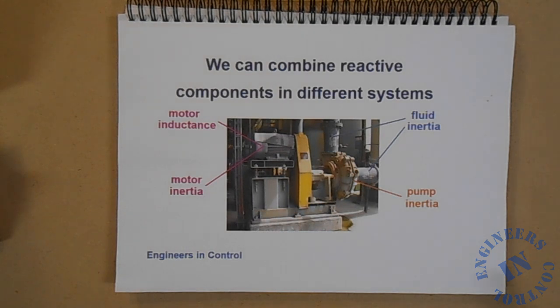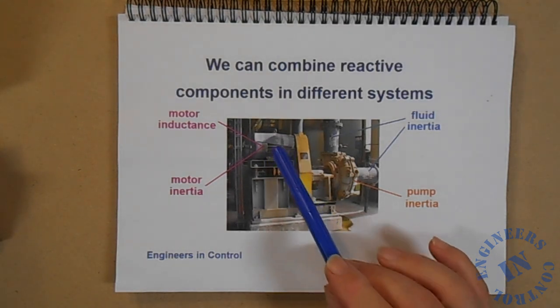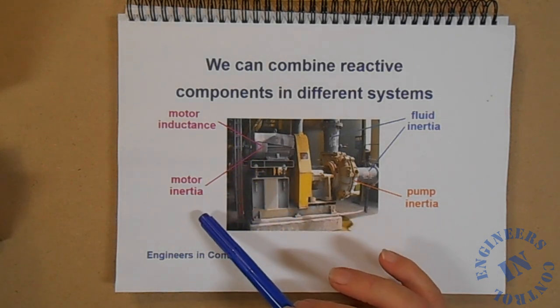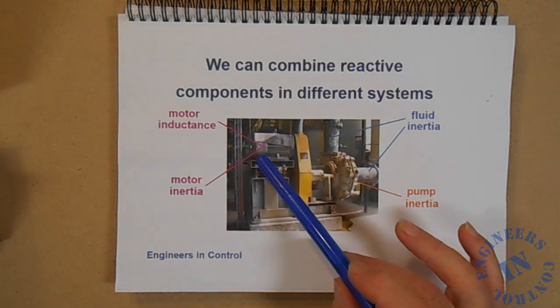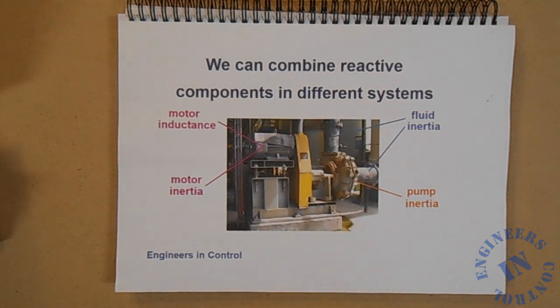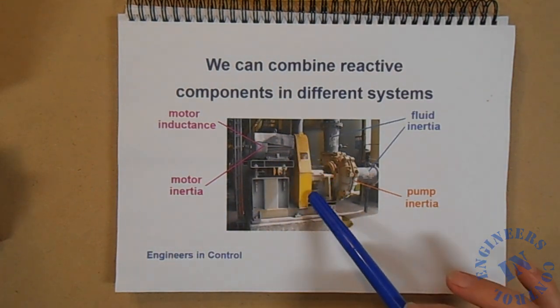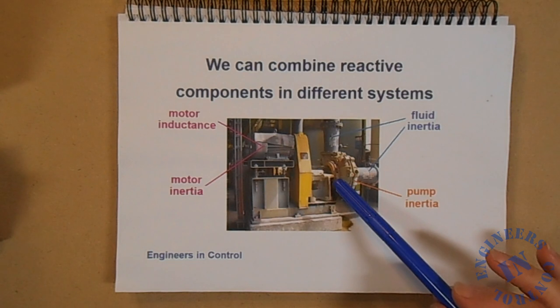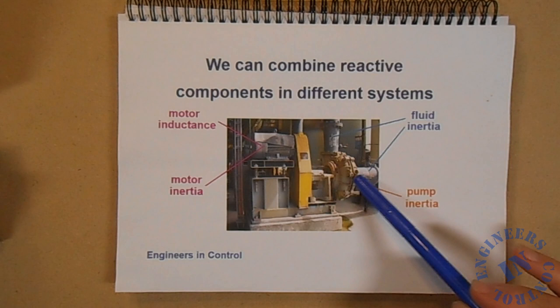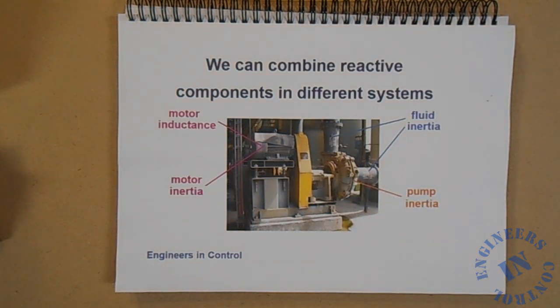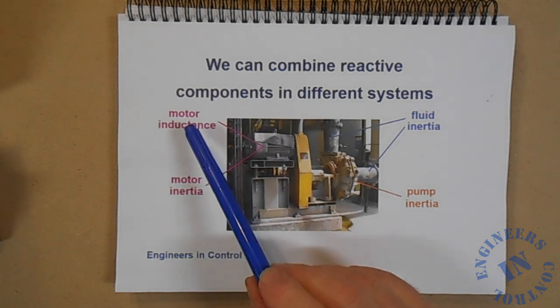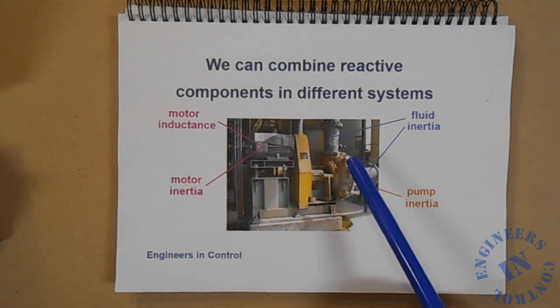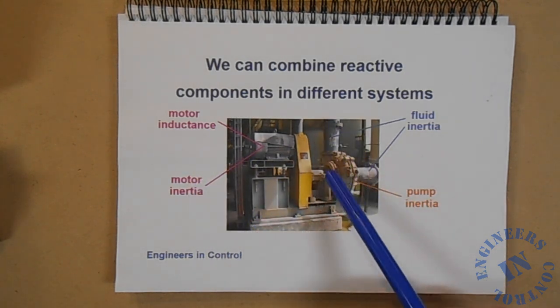As we saw, we have a motor with inductance as a reactive component and we also have the inertia of the armature. It's coupled by a chain drive usually to a pump. Here's the pump. Now the pump also has inertia and that's a reactive component. But we have fluid in the pipe work and the fluid has inertia too. So we have effectively four reactive components: inductance, inertia in the motor, inertia in the pump and inertia in the fluid flow.